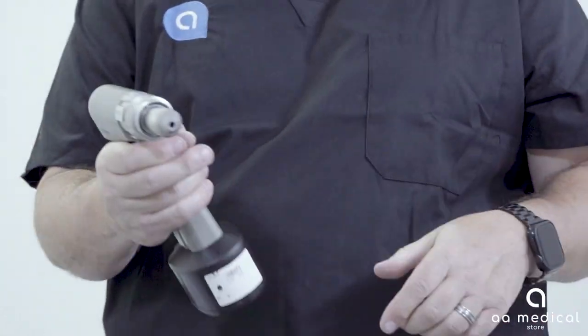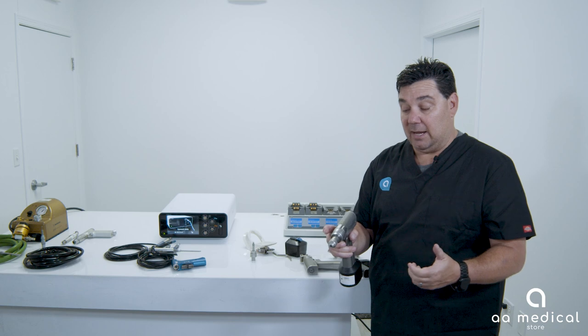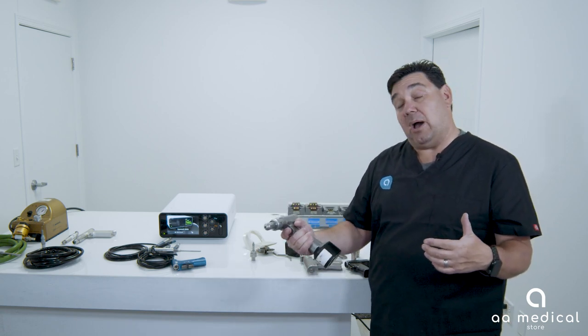With System 6, it's a higher, heavier, bigger handpiece, and the chuck — where the handpiece connects to the attachment — is different. Because of that difference, you would need different attachments. It clicks in and then you can drill or ream. It's a higher-torque handpiece used in bigger bone procedures, but surgeon fatigue is a factor because the handpiece weighs considerably more than a micro or corded system.